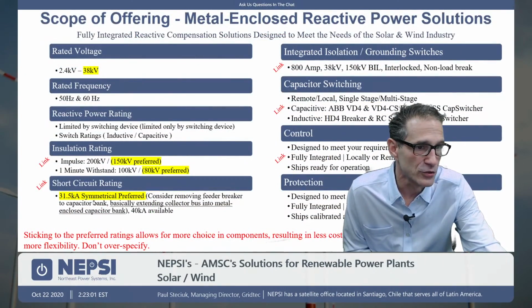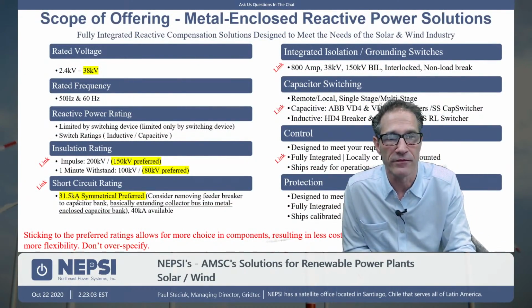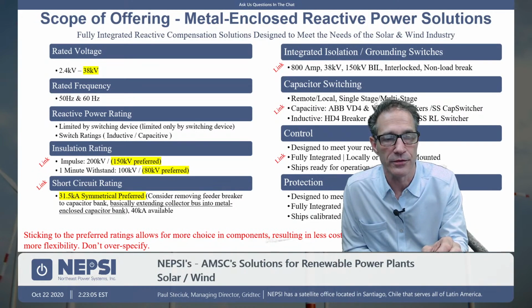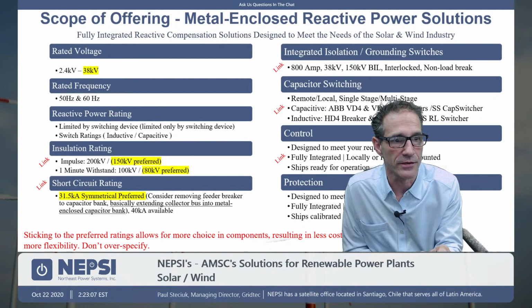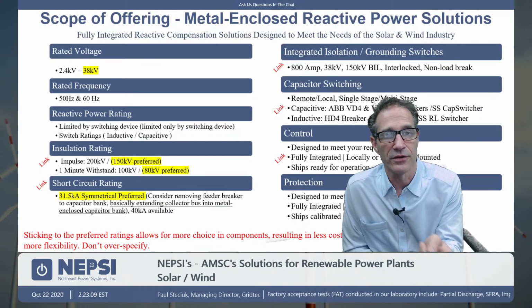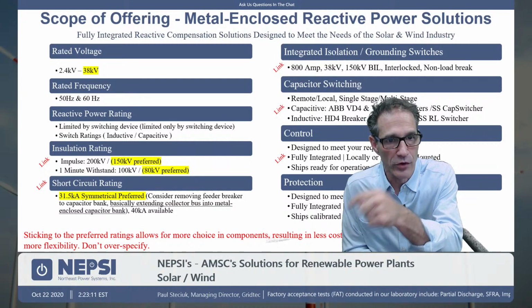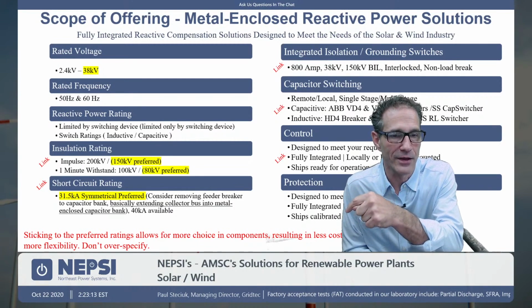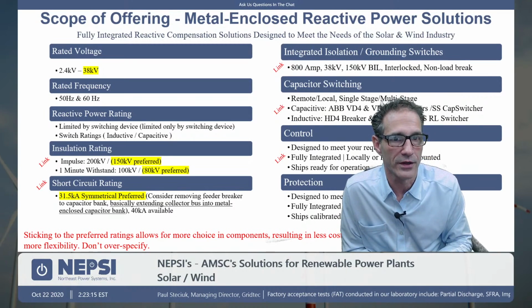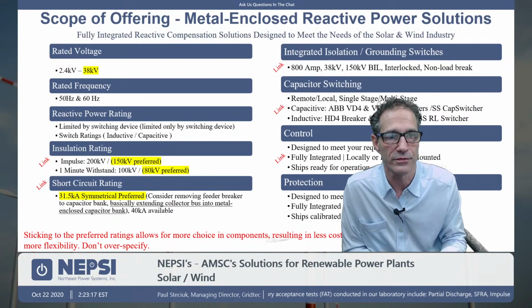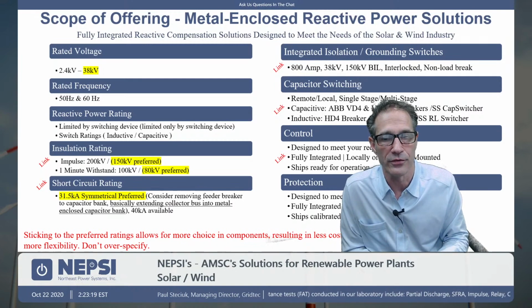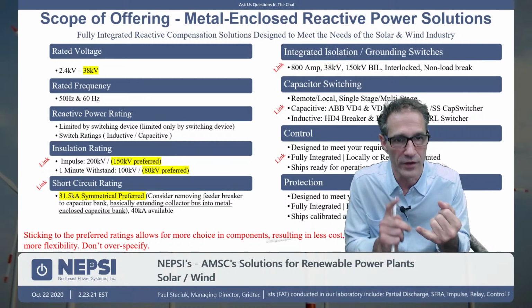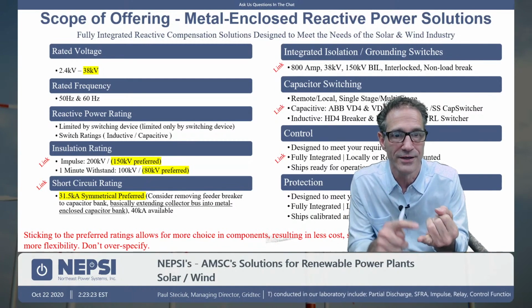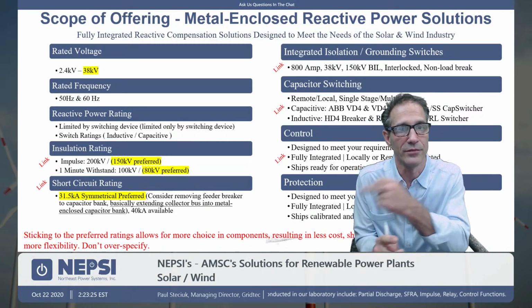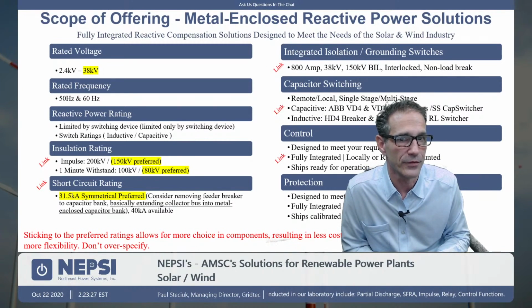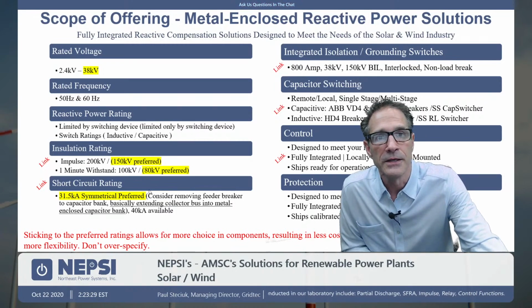So short circuit rate, if you specify 31.5 kA, we can use those breakers and we can use the switching devices. And what it really is going to do is help you eliminate the feeder breaker in front of the cap bank. And we're going to show a one-line diagram of a typical collector system to show you how that breaker inside our equipment can serve a purpose for both switching and short circuit protection, and we can eliminate an upstream feeder breaker. So a key thing to think about.